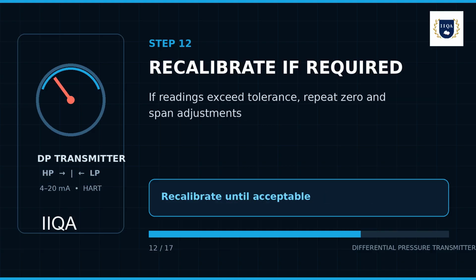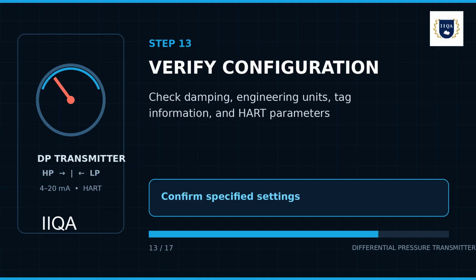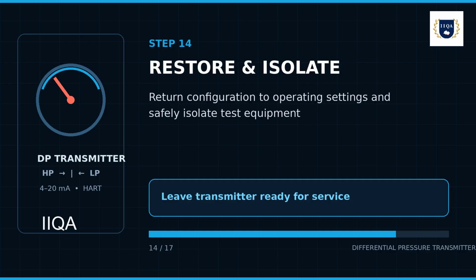12. If any readings are outside the allowable tolerance, repeat the zero and span adjustments and recalibrate until acceptable results are achieved. 13. Verify transmitter damping, engineering units, tag information, and HART configuration parameters, where applicable. 14. Upon completion of calibration, return the transmitter configuration to its specified operating settings and isolate the test equipment safely.